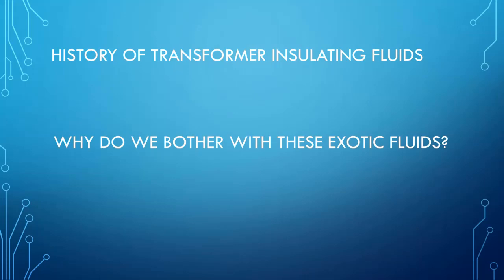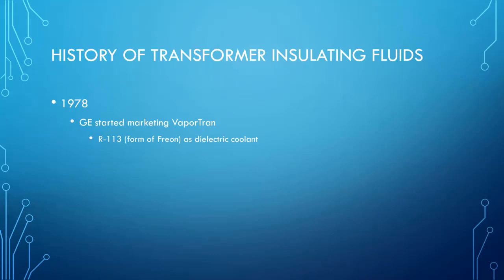Inventors and chemists began toying with different ways to insulate a transformer. This is not the first fluid, but it's worth noting. Transformer manufacturers tried things like Freon, which was effective, but environmentally terrible. Westinghouse marketed a product in the 60s called Wecosol, a dry cleaning fluid, and again effective, high fire point, good dielectric strength, but again terrible for the environment. And these are in a class of fluids we call non-flammable fluids.